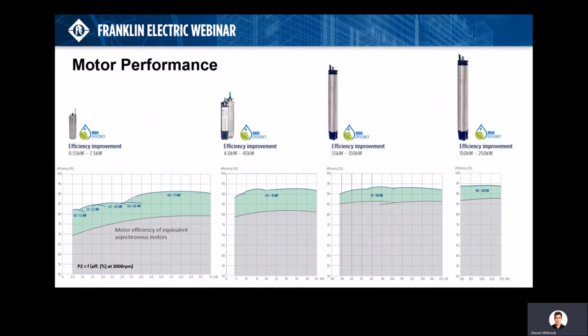Important to say is that all of our PM motors, regardless of the size, offer that outstanding improvement in efficiency throughout the complete range. Now, as you can see, going from left to right, the PM motors improve efficiency on average by about 15% compared to an equivalent standard motor. On the other hand, you see that the motor efficiency curves are very flat, which lets you use one motor in a certain performance range.